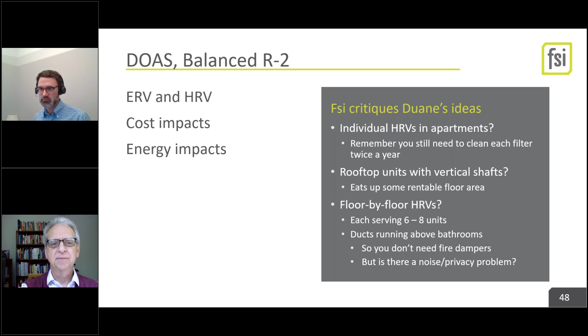But in general, as I said before, it's going to have a 7 to 10 year payback. It's good energy. The only downside is the tenant benefits this one. So for the building developer, if you're individually submetering tenants, you've got to find a way to make the value proposition, like, look how low your energy bill will be if you live here, and I get to charge you a little more for that. That's the only way to make that value proposition. Our state law says that it's cost effective for owners and tenants - it did not say it's cost effective for builders and developers necessarily.